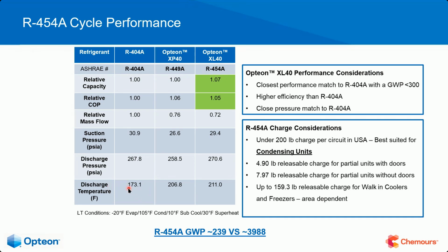All right. So 6 inches out from 404A, we typically on a good running system is around 173. Now, don't hold me to this. It's not etched in stone, but this is what it looks like in the labs. For 449A, it would be approximately around 206.8. And then for the new equipment, 454A will be somewhere around 211. All right. So GWP for 454A is 239 versus 3,988. Come up here and look. Opteon XL40 performance, closest performance match to 404A with a GWP of less than 300. It's higher efficiency than 404A, and it's a close pressure match as we talked about.